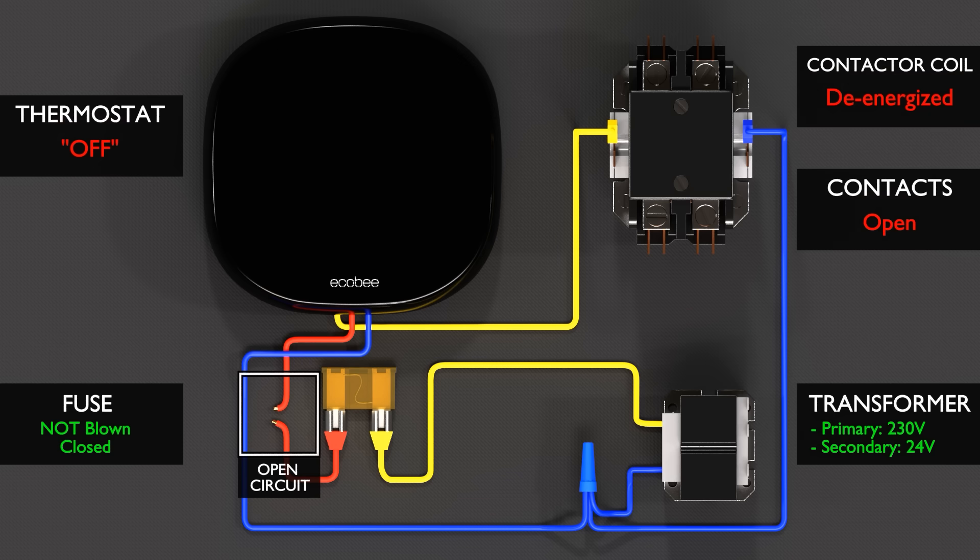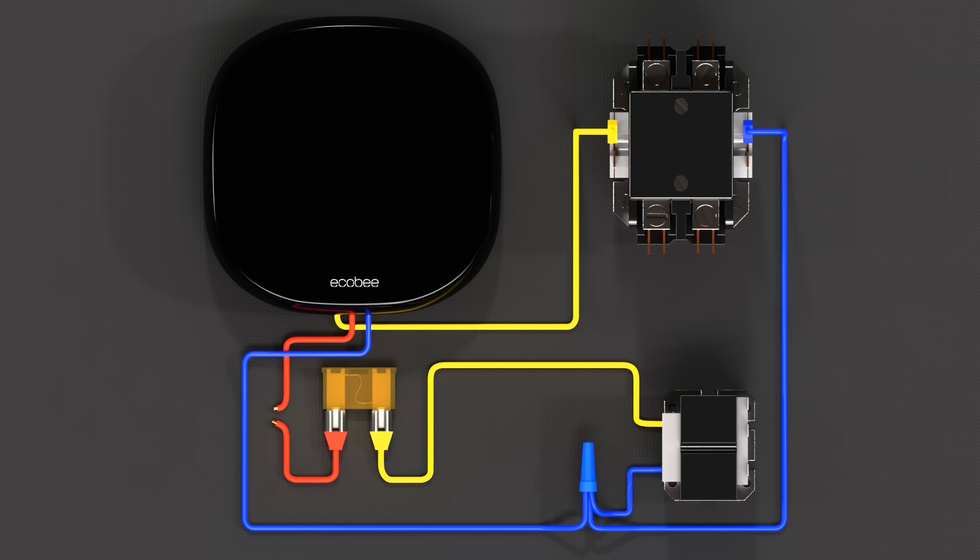When the R circuit is open, the thermostat is off. The fuse cannot be blown by an open circuit, but the contactor cannot energize, and the contacts remain open. Therefore, the system does not run. In this case, the open circuit is shown as a broken conductor or wire.